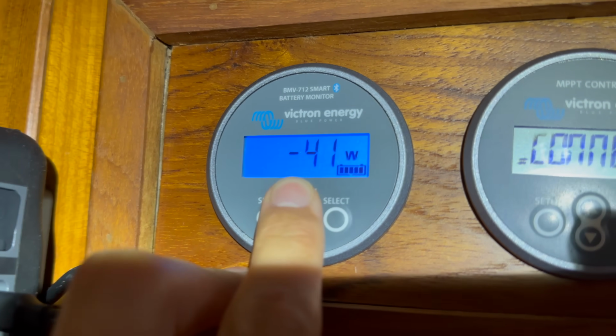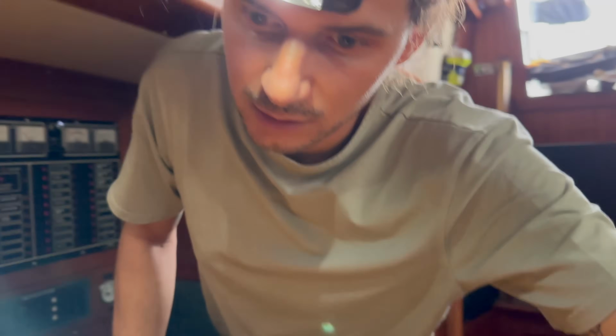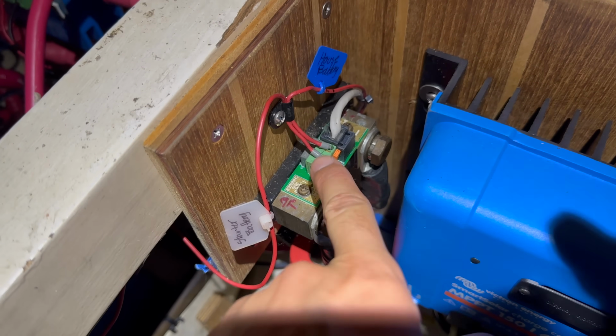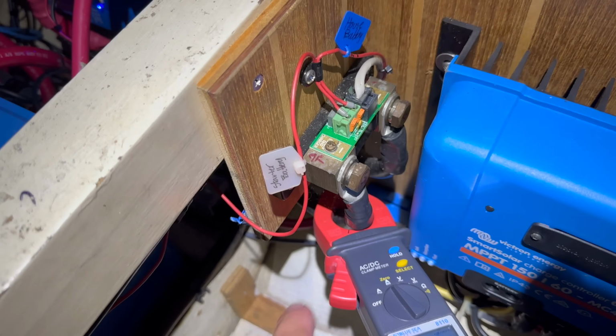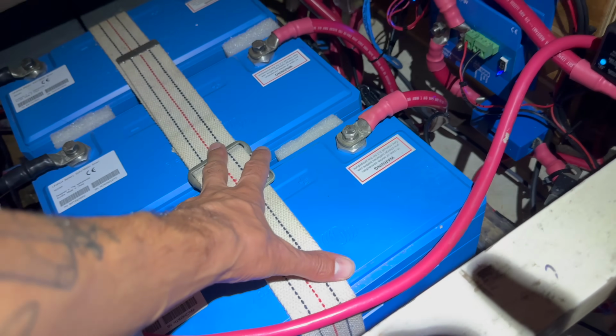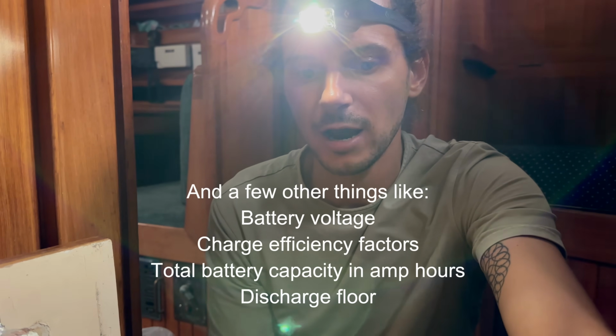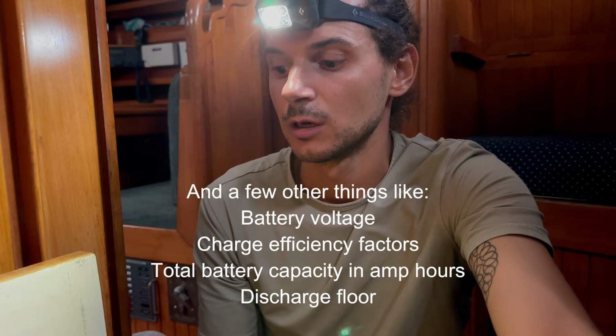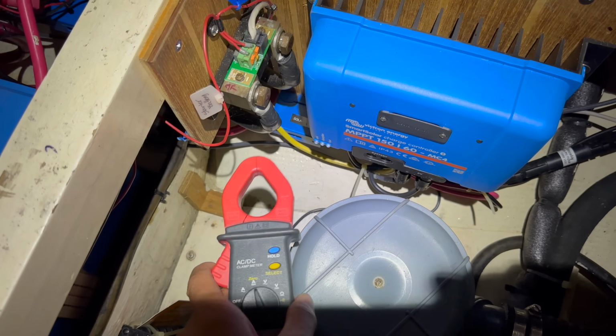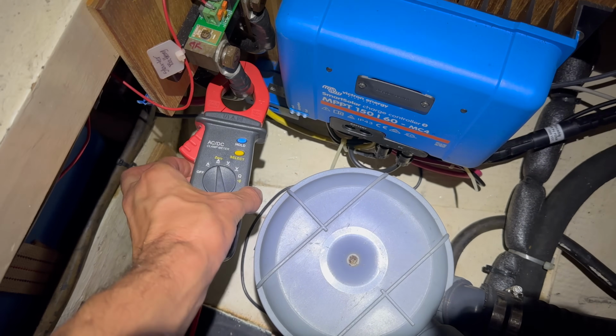Now the battery monitor is just a calculation. There's an algorithm that estimates it. It's only for end user monitoring of the battery system, and it has nothing to do with the actual battery charging or depletion. All it is is a shunt, right here on the negative side of the battery system. Through this little circuitry it goes over to the battery monitor, and the algorithm does the computing, telling you how many amps are being pulled out of the batteries or going into the batteries. It then uses that information to calculate the state of charge in percentage from 0 to 100, and how much time you have left depending on how much amperage you're drawing at any given time. This is just a clamp you can put around any 12 volt DC wire, and it'll tell you how many amps are going through.